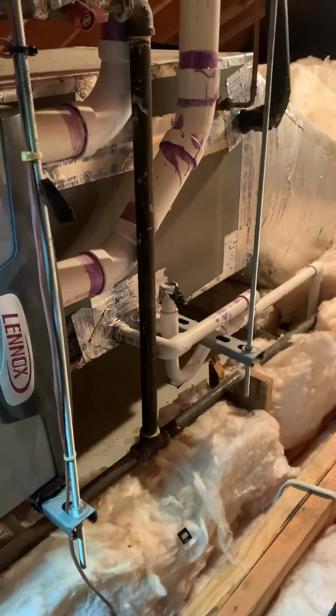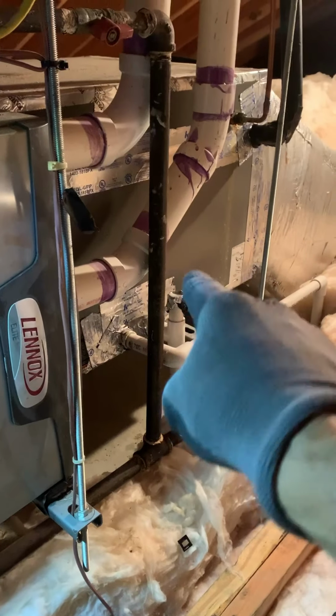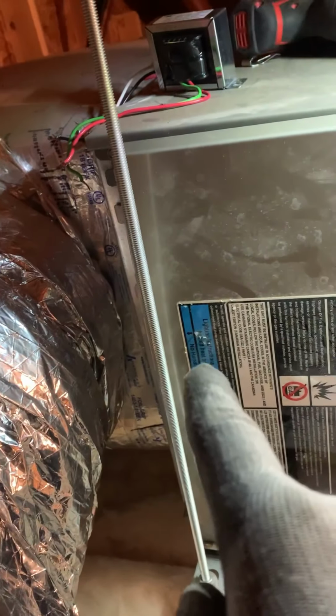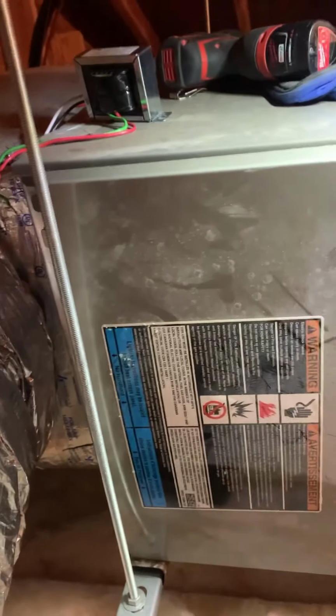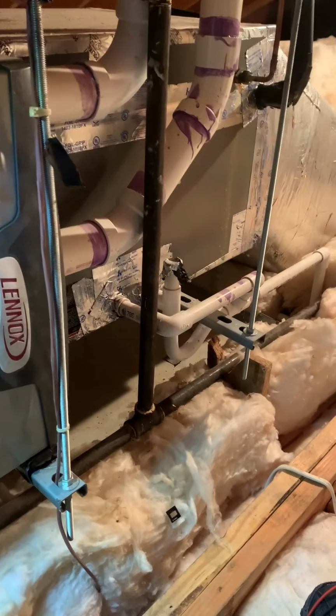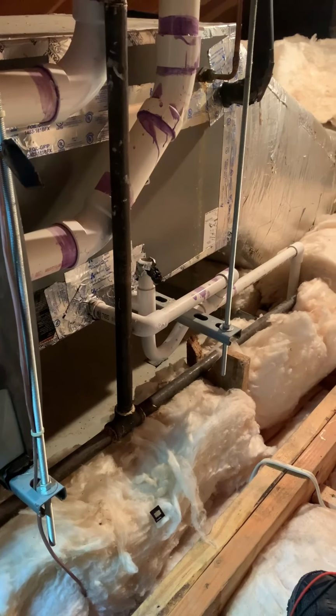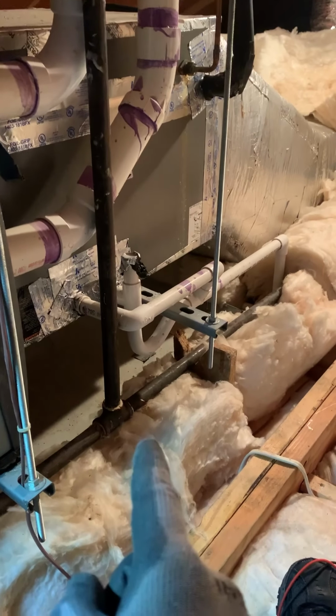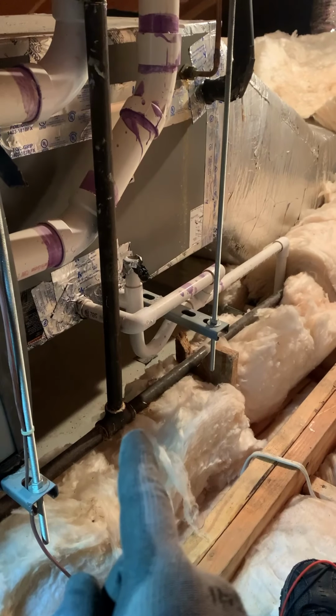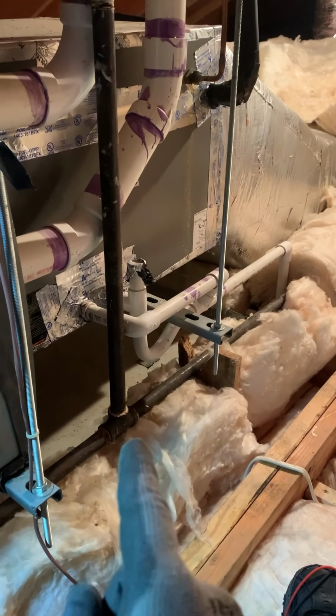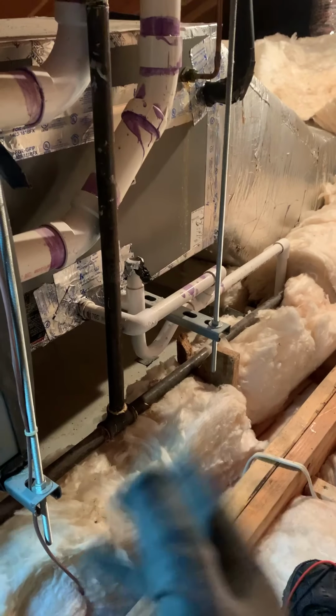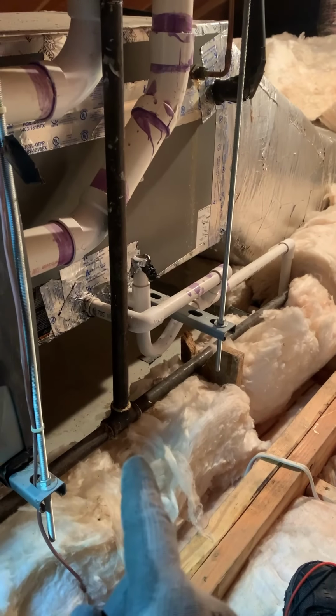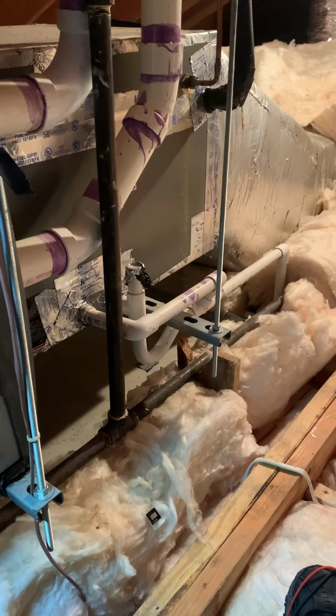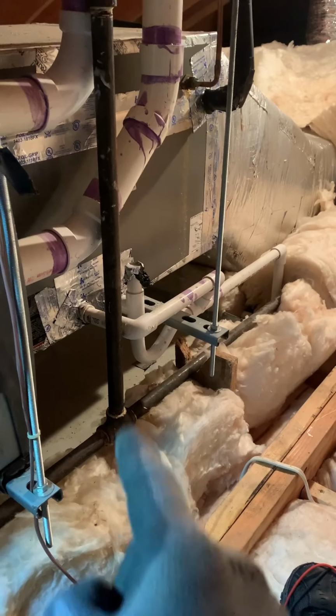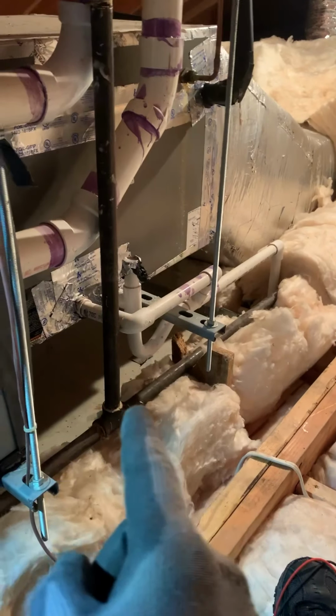So if you ever see a positive coil, it's called a positive coil. If that coil was here, right next to the return before the blower, that would be a negative coil. Negative coils need a trap. Positive coils do not need a trap. So I'll let the customer know that they really don't need a trap here, and that gets clogged up a lot. I don't really see it too much with the straight pipe. You know, the clog might be on the outside or something like that, but just for the technician's knowledge, positive coil: if the coil is after the blower, then no trap.